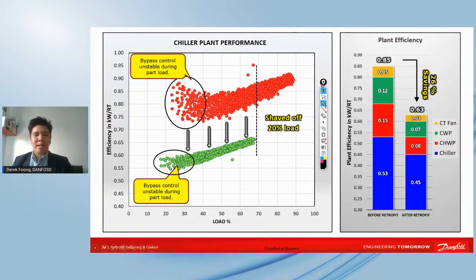Let me ask engineers who actually deal with chilled water systems: how many times do you go to the site during low load, and how many problems pop up whenever it's nighttime or low load? You always get called to the site to attend to problems, and you get BMS guys and chiller guys, and it seems that part load is the most unstable time, and that's where most problems occur.